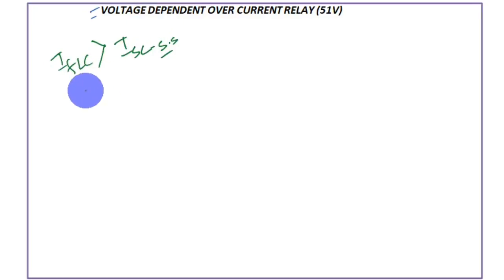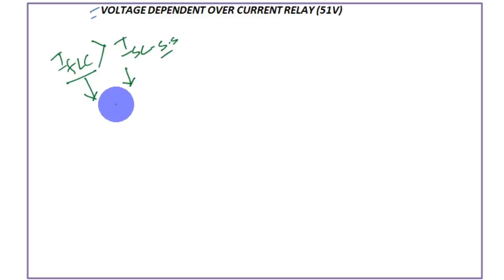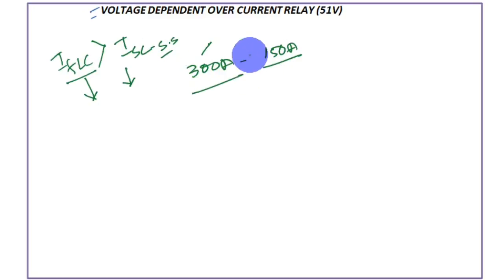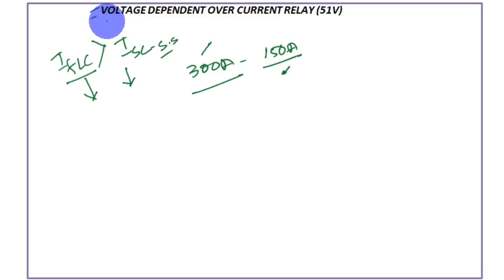In that case, if you have to select a relay pickup, you have to keep it higher than full load current but lower than short circuit current — which is not possible. Suppose your full load current is 300 amperes and your steady state short circuit current is 150 amperes; you would need to select something higher than 300 but lower than 150, which is practically a fallacy. To counter this, a voltage dependent parameter must be introduced.